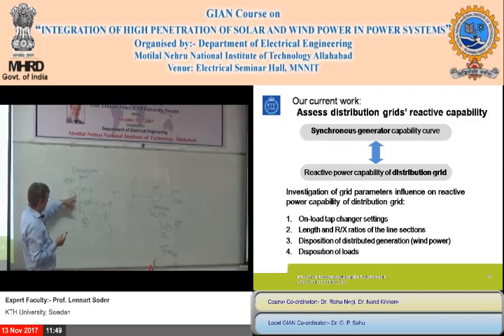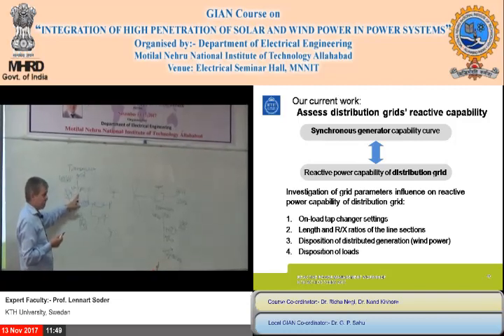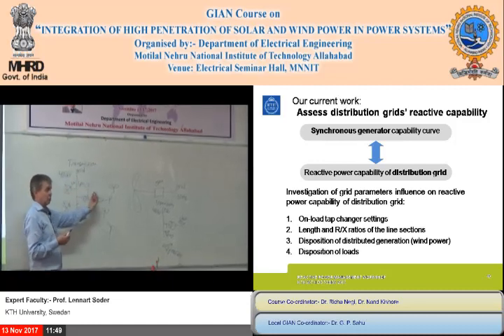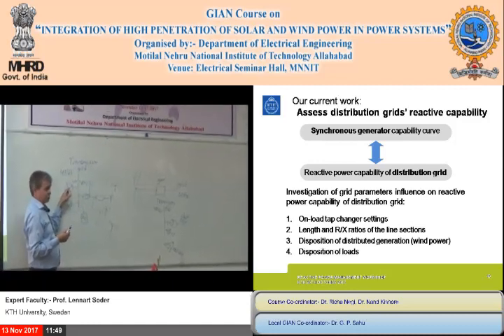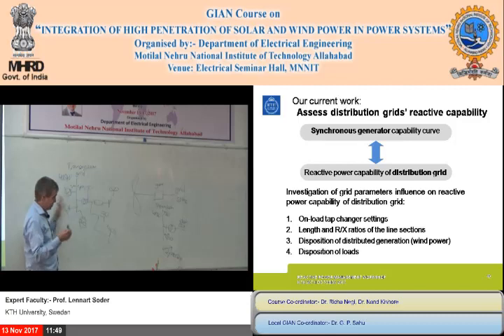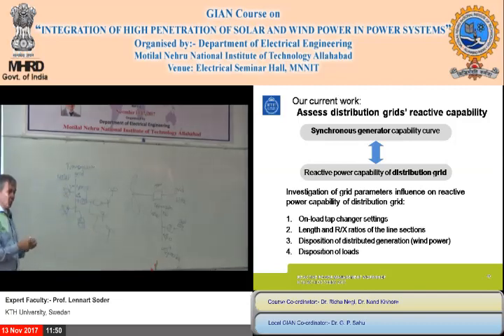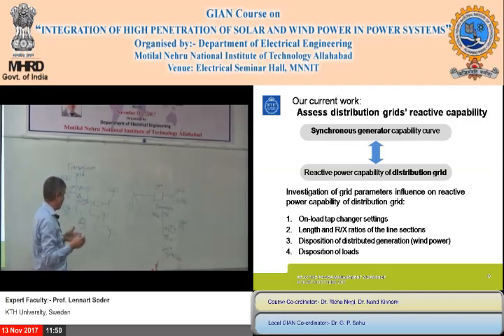These generators are normally keeping the voltage here, meaning they supply or consume reactive power, with a simple voltage control. The question is, if you take away these generators, you want the wind power owners to do the same. From the transmission system operator's point of view, they want to see this interface: if the voltage goes down, they want more reactive power; if the voltage goes up, they want to send out reactive power. So they want a distribution grid with wind power to work as a synchronous generator.